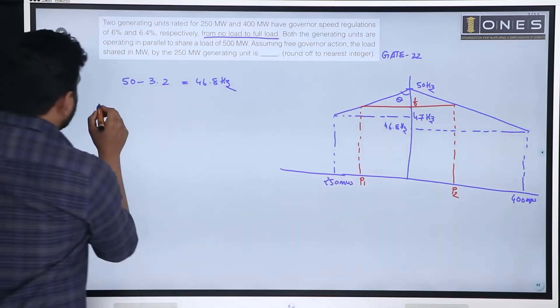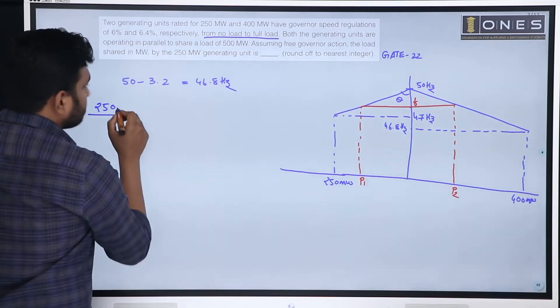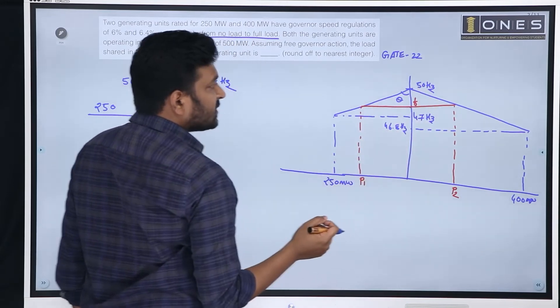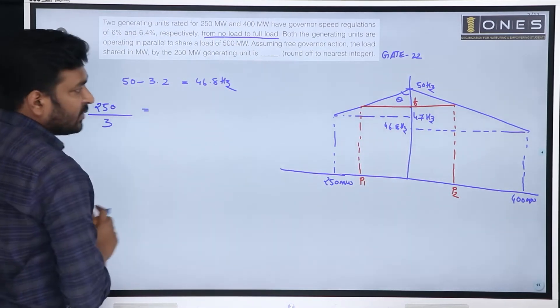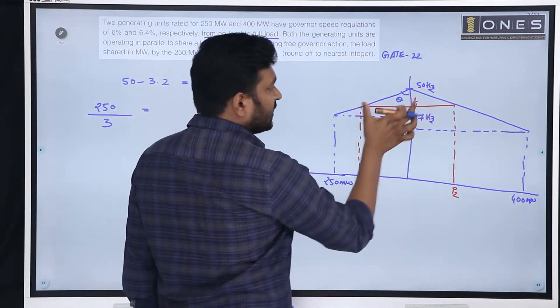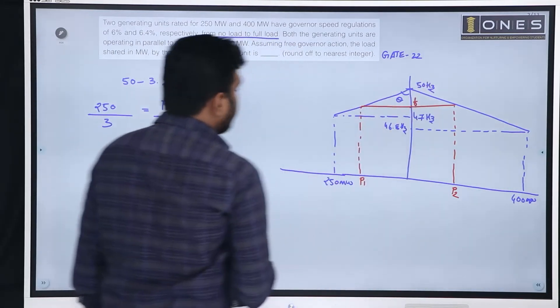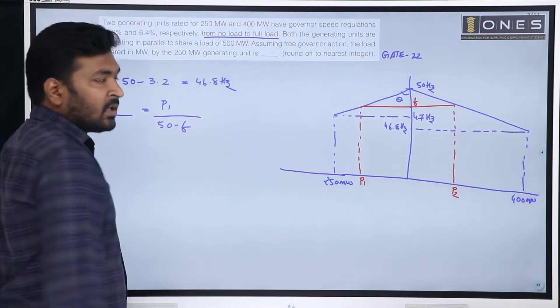Opposite is 250 megawatt. So, 250 megawatt divided by 50 minus 47, which is 3 hertz. This is equal to the triangle opposite by adjacent, which is P1 divided by 50 minus F.